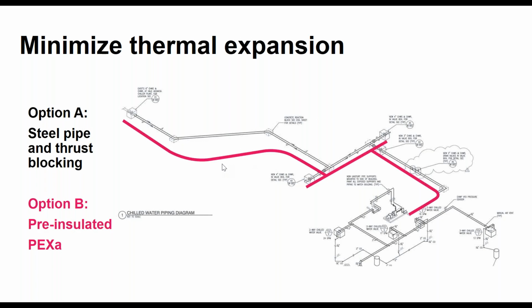Instead, with a set of plans, we'd bring our highlighter and mark it up like this, showing we can go from point A to point B with minimal fitting. We're taking all those thrust blocks out, and we've got two T's here, then a termination by the pump in the mechanical room or wherever. On this side we're going all the way back to the boiler or chiller plant. For 4-inch pipe, that's a pretty big deal, and that's usually one of the ways we get the attention of a design build firm tasked with getting from A to B.